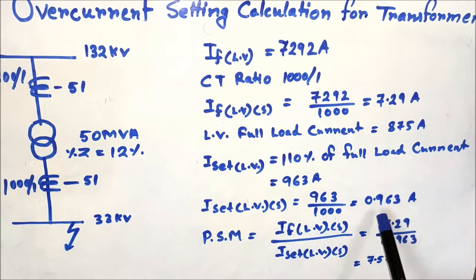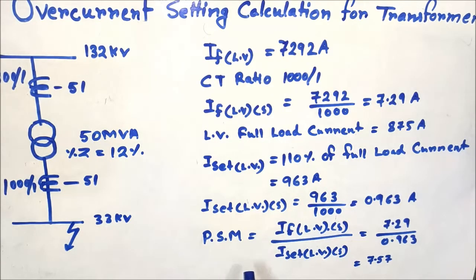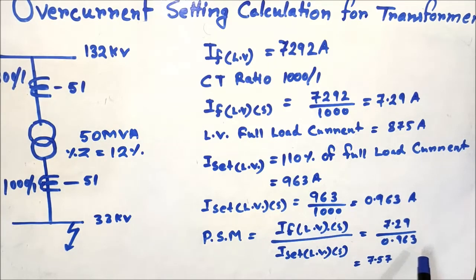This is the current setting value for the LV overcurrent relay. Now, the plug setting multiplier (PSM) for the IDMT curve is the relay fault current divided by the setting value. The fault current sensed by the relay under maximum fault conditions is 7.29 amperes, and I_set is 0.963 amperes. Therefore, PSM equals 7.29 divided by 0.963, which comes to 7.57.